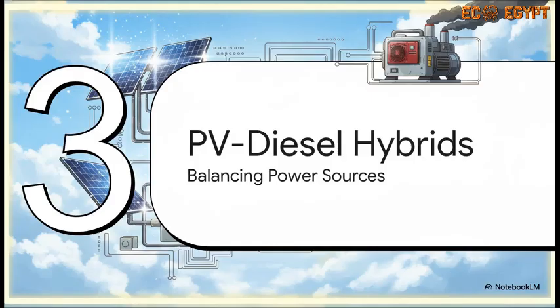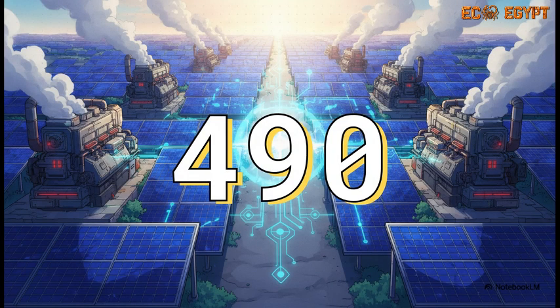Section 3 brings us to PV diesel hybrid systems. 490. That is our anchor number for this specific design. We're looking at a 490 kilowatt peak DC capacity system. But honestly, the real magic isn't just in the massive footprint of the solar array itself, it's actually in the incredibly complex control logic required to seamlessly balance clean solar energy with roaring diesel engines, entirely without causing grid instability.